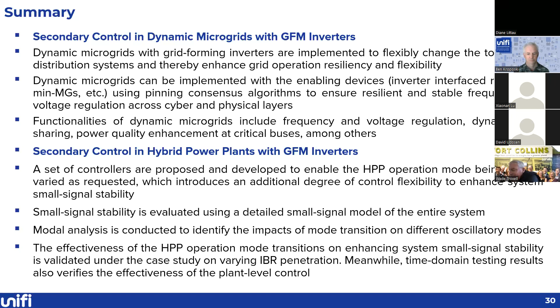The second application of our proposed work is about hybrid power plants with grid forming inverters. We developed a set of controllers to enable different types of operation modes and smooth transition between them in the overall system. We focus particularly on small signal stability enhancement in this framework, and we performed modal analysis to verify that operation mode transition can actively enhance system small signal stability as an additional layer of controllability.